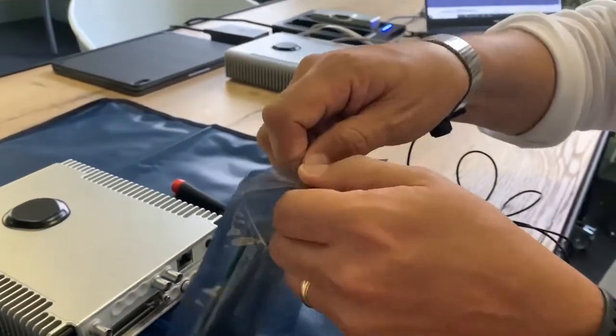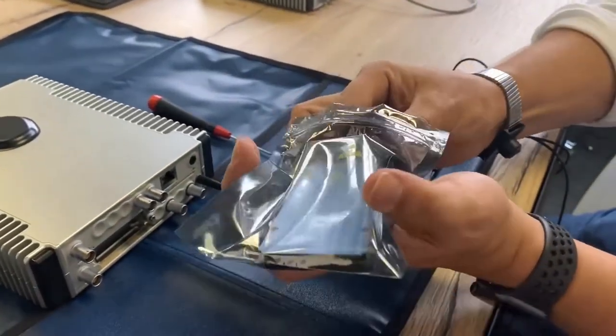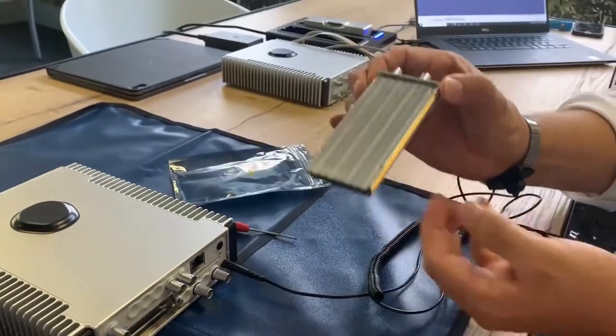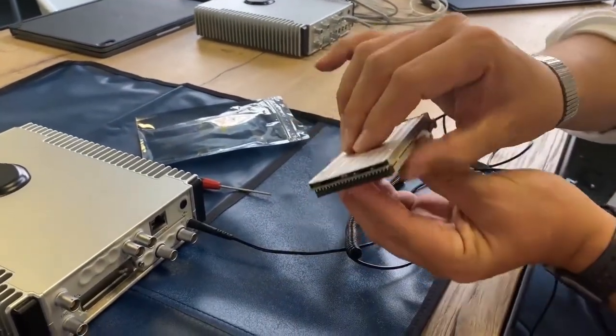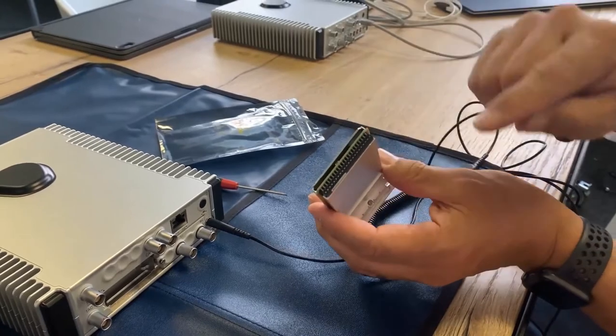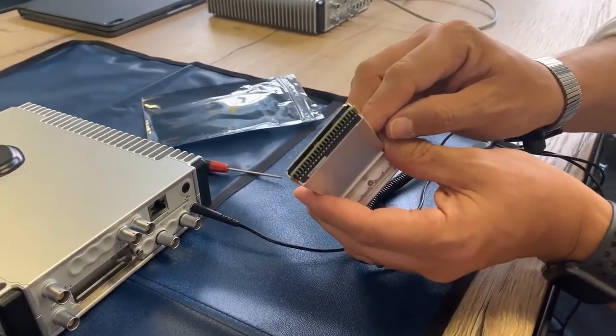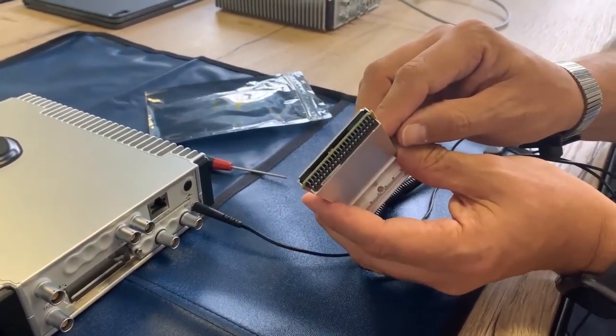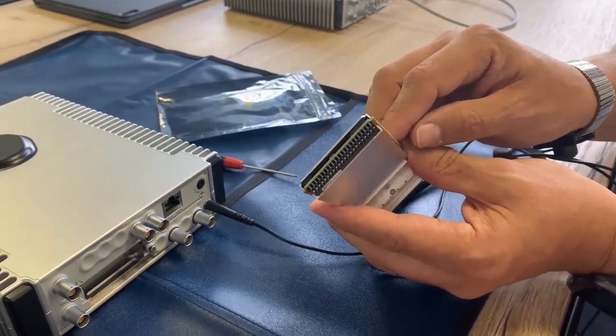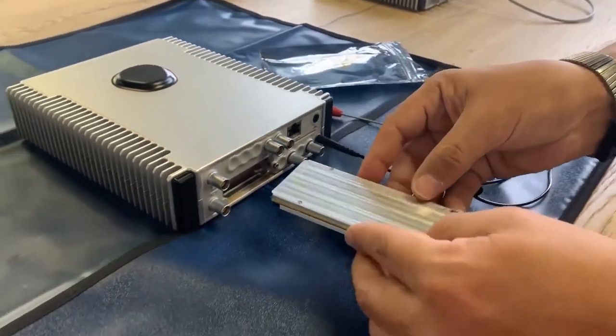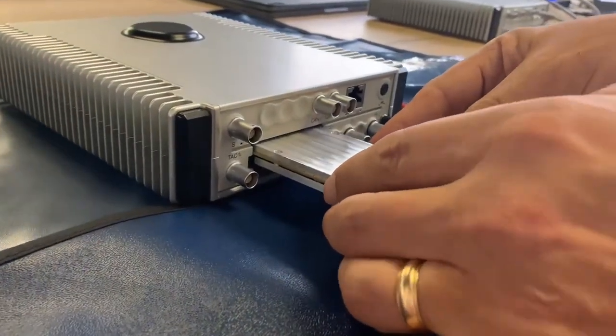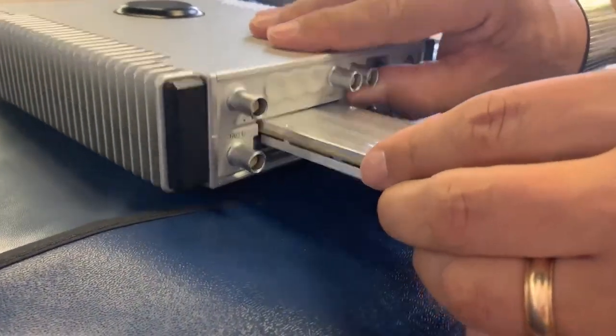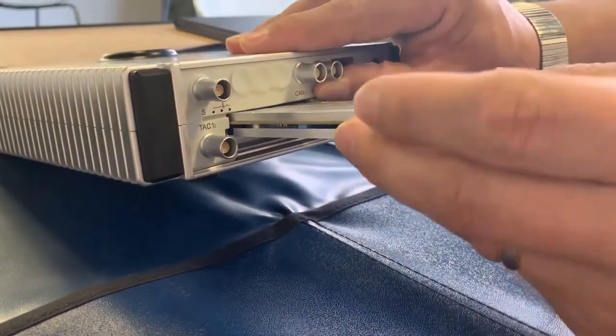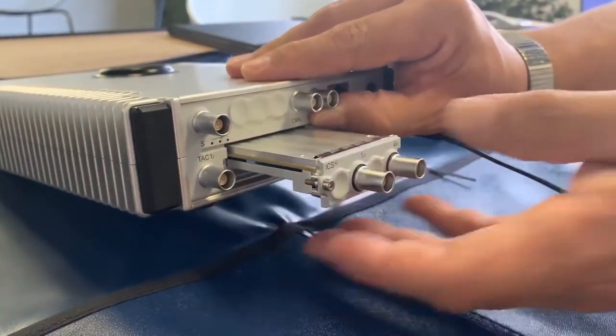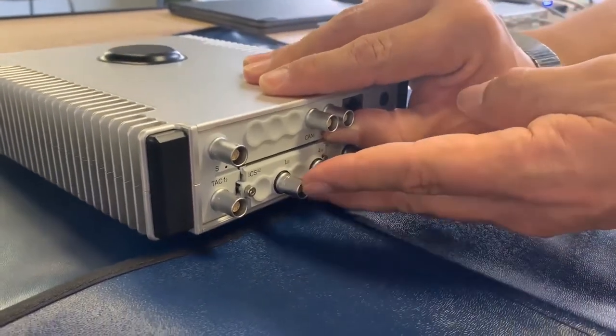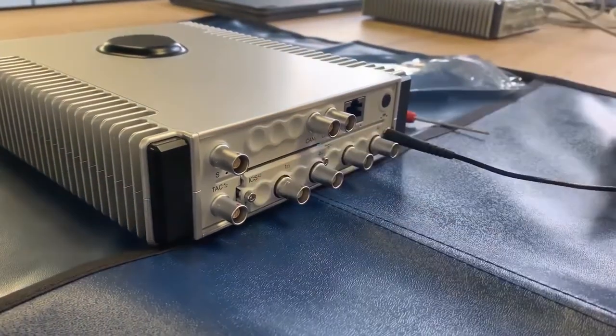When you go to remove the module from the ESD bag, please make sure that you handle it from the front or the side, tops or bottoms, but you should never touch the connector across the back. That's the greatest potential for an ESD discharge that will damage the module itself. So now we just insert the module into the MICROQ. And you can push it in until the jacking screw engages.